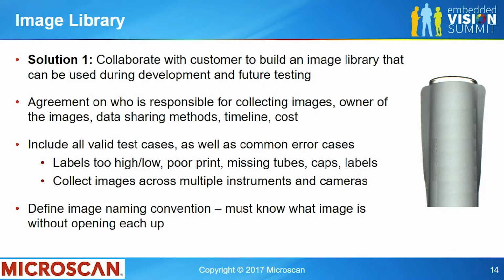Again, I mentioned knowing all the use cases. You need images, multiple images for every use case and all the error use cases that you can think of so that you can test it and make sure it's working appropriately. In a test tube sample, this might be where labels are too high or too low. There are standards for all of that. It could be that there's no sample in the window at all. It's just a blank picture. What do you do when that happens? It could be a cap on or off. It could be any sort of thing. And you need to make sure to collect these images from multiple smart cameras, multiple instruments, multiple users to have a wide variety of samples to be looking at.